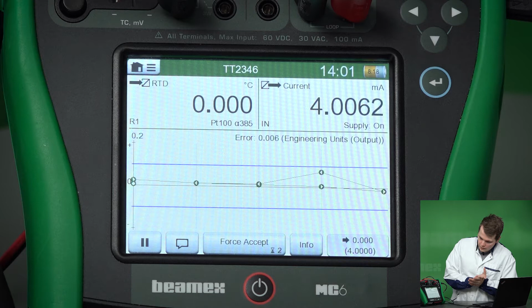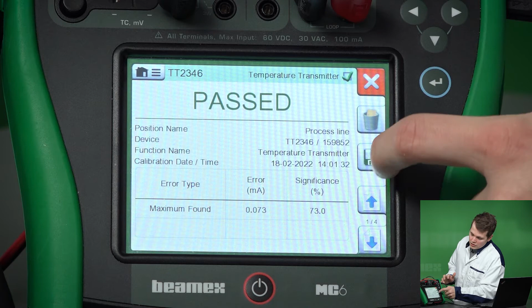So all we have to do is wait for the MC6 to go 5 points up and 5 points down, and then we will be able to save the calibration results. Let's wait for that to happen - I believe we are on our last point. There it is, so it's been accepted now and the calibration has passed. I will save this as found, and now the results are located in the MC6.